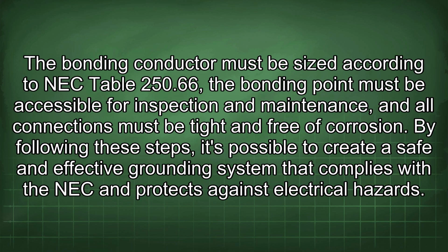The bonding conductor must be sized according to NEC Table 250.66. The bonding point must be accessible for inspection and maintenance, and all connections must be tight and free of corrosion. By following these steps, it's possible to create a safe and effective grounding system that complies with the NEC and protects against electrical hazards.